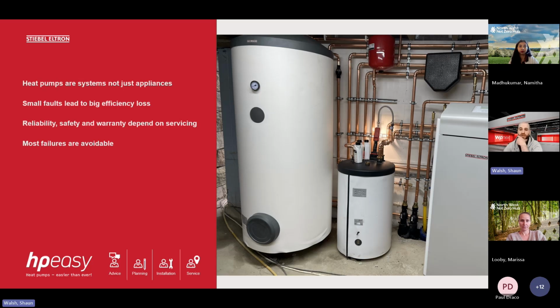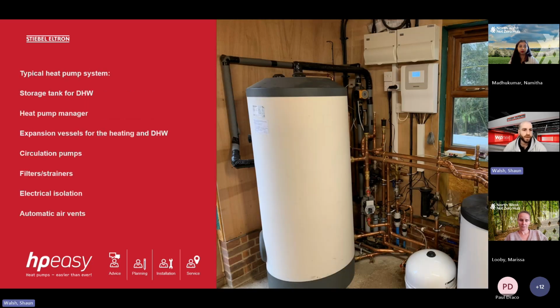Some of the common issues you might see are people might complain of a noisy unit or higher energy bills, low output of the machine, and with it relying on sort of airflow as well. If it's an air source heat pump, you can get flow restrictions and things like that with the air source heat pump.